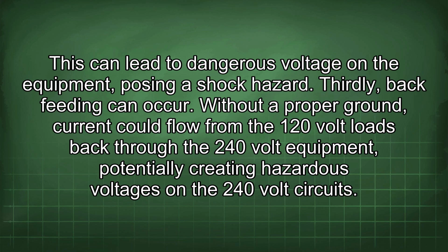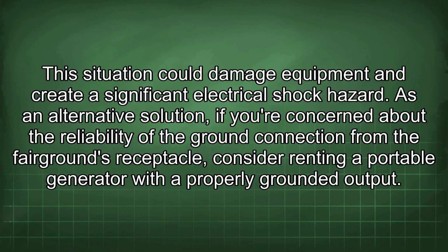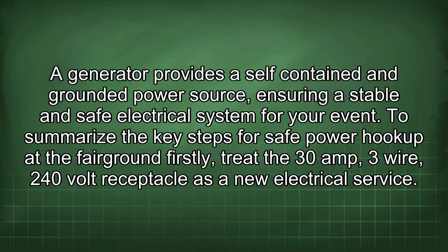Thirdly, backfeeding can occur. Without a proper ground, current could flow from the 120-volt loads back through the 240-volt equipment, potentially creating hazardous voltages on the 240-volt circuits. This situation could damage equipment and create a significant electrical shock hazard. As an alternative solution, if you're concerned about the reliability of the ground connection from the fairground receptacle, consider renting a portable generator with a properly grounded output. A generator provides a self-contained and grounded power source, ensuring a stable and safe electrical system for your event.